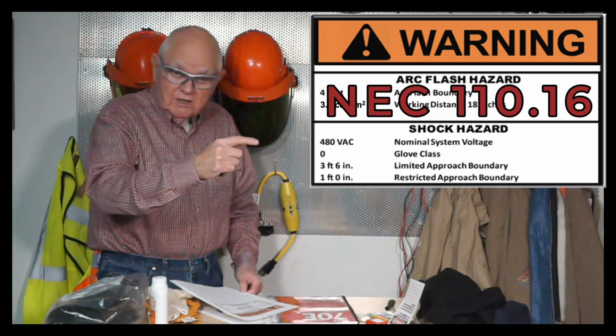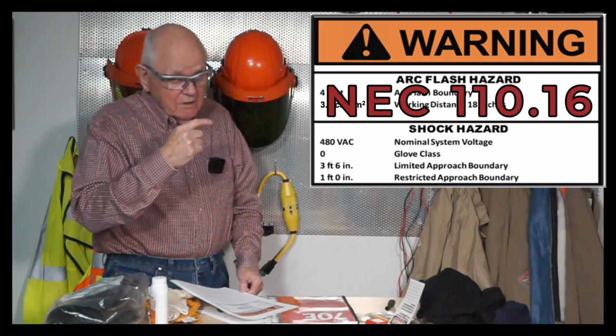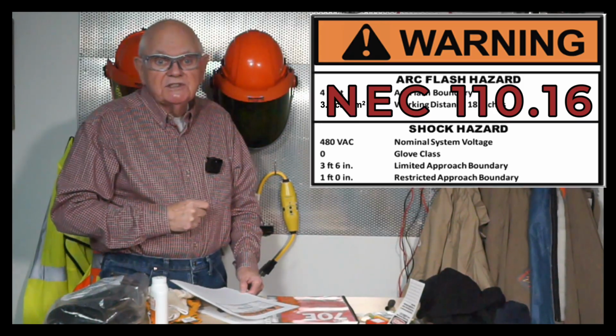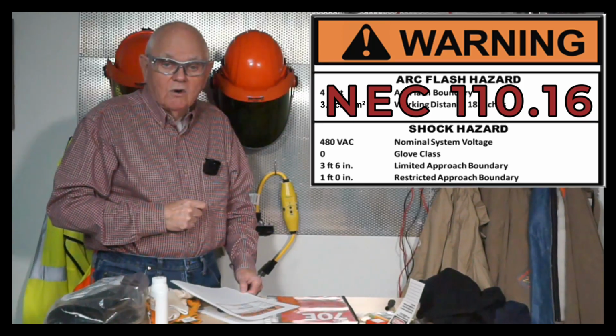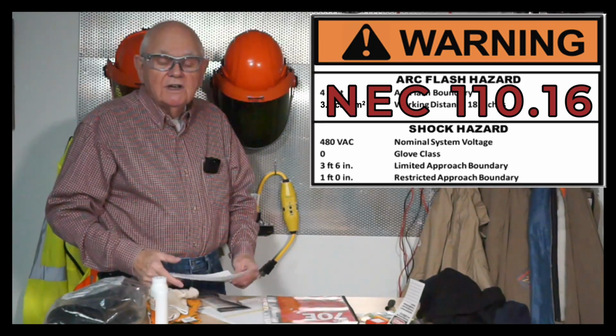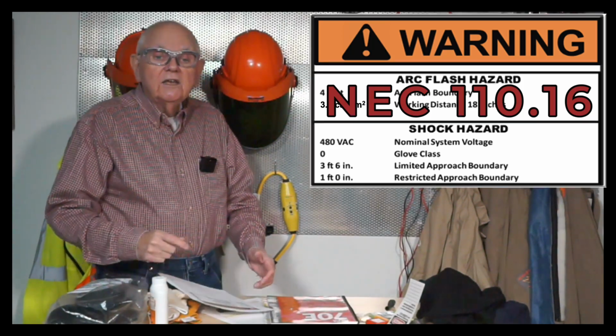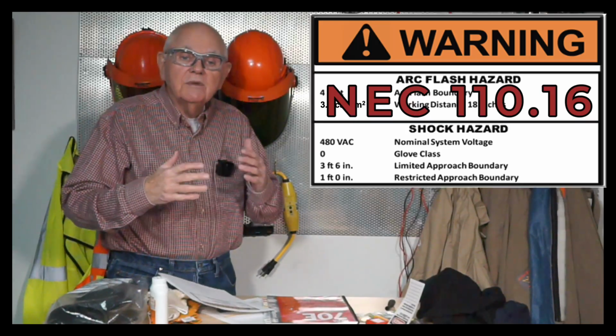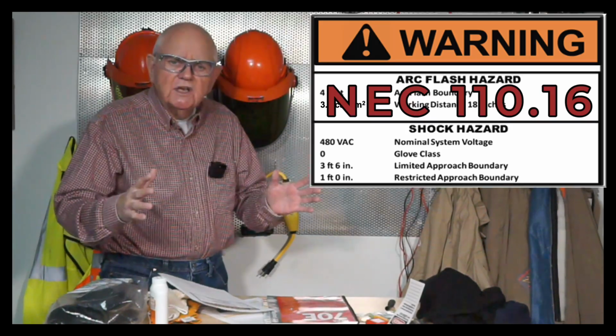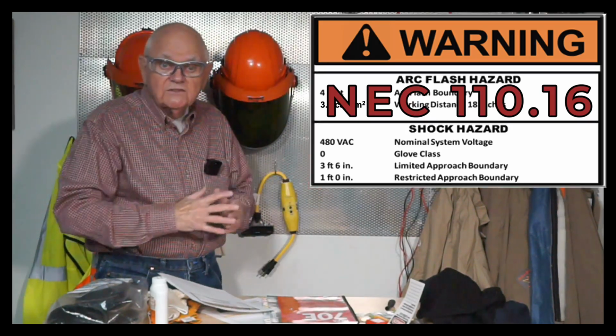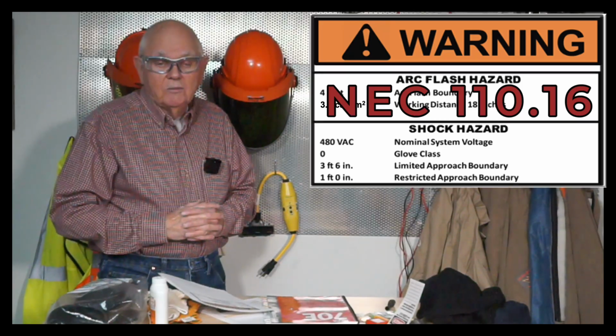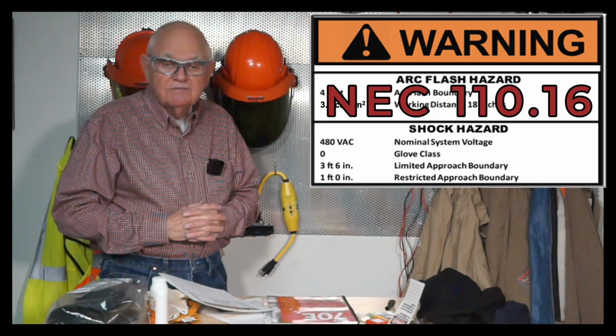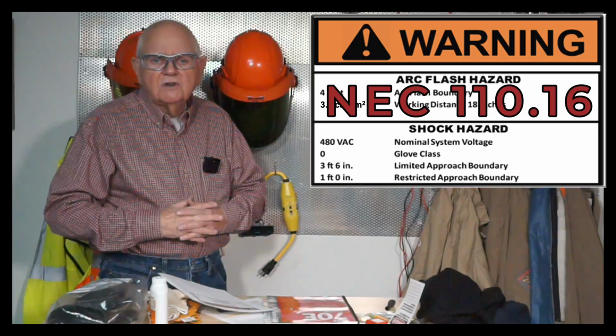By the way, later on in 2025, we may well see some changes to 110.16 for arc flash labeling requirements. But nonetheless, what's in place right now, 110.16, covers any equipment that's likely to require servicing or maintenance after installation, and it gives us a whole list of examples. We're required to have some type of warning label on the equipment to warn people of those hazards. It has to be durable and legible and so on and so forth.